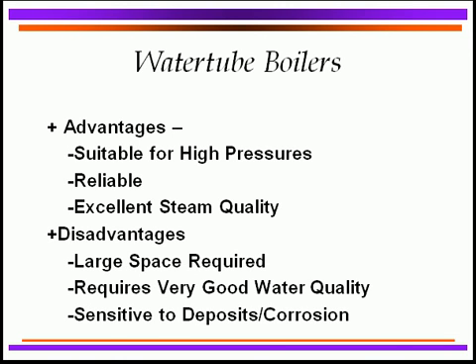That steam quality is very, very good because if we need to be driving turbines and using them for process operation where it requires excellent steam quality, the water tube boiler just excels in that area. Some of the disadvantages of the water tube boiler are that it requires a lot of space and certainly requires very good water quality as contrasted to the fire tube boilers. There is a concern because of the higher pressures and higher temperatures involved — water tube boilers are much more sensitive to deposits and corrosion.